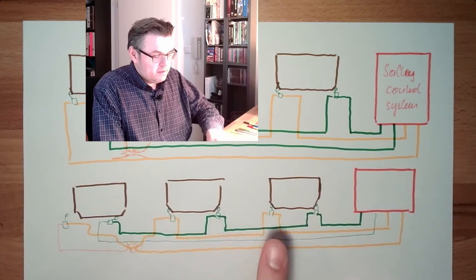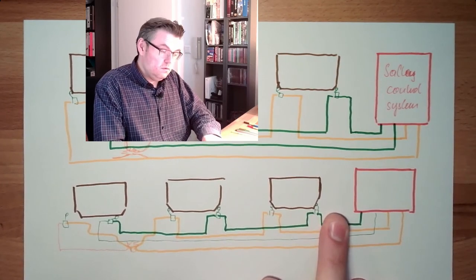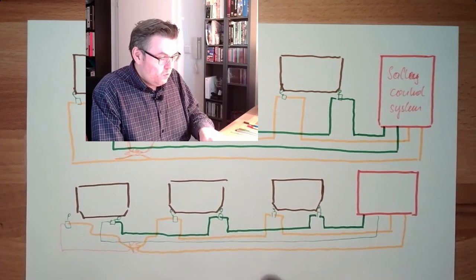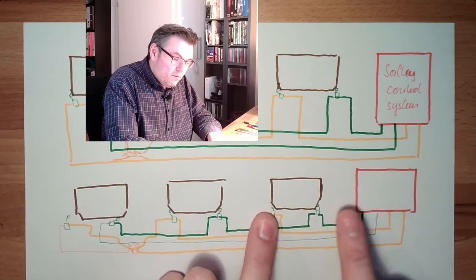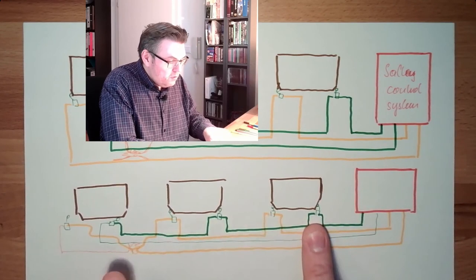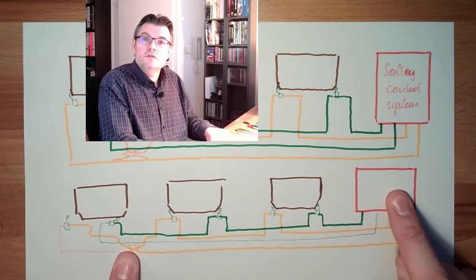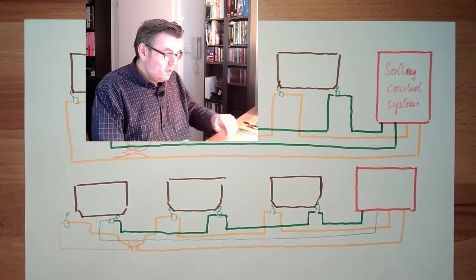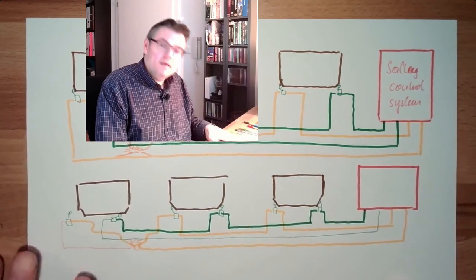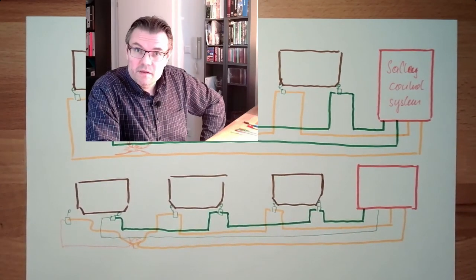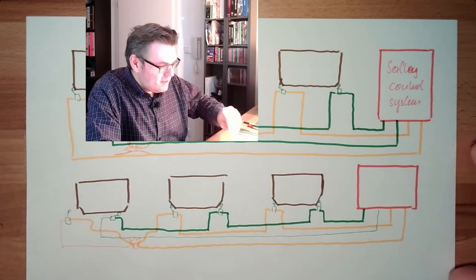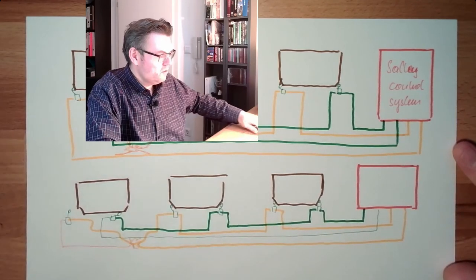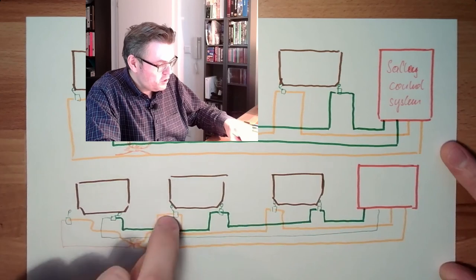Even if I close this door then and it looks okay, this is also not giving it free. Because it needs then to reach the safe area. It needs the reset area. And this reset area is both must indicate they are open. Because that is where the error happened. So however I can do it like this. I can open the door. So if I open the door, then I will, it will look like, because all of those will switch off. I will also switch off the short circuit. For the safety control system it looks okay. Then I close this door. Then I close this door. The door is still operable. Still the error is still inside. And the machine can operate. So this is an issue. This is an issue. This is why this is not suitable for category 4 security levels.